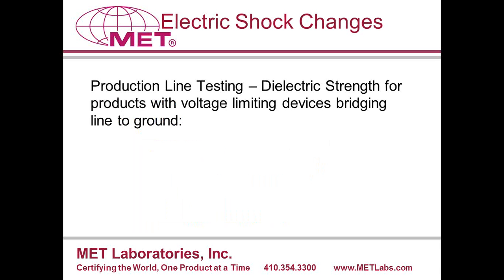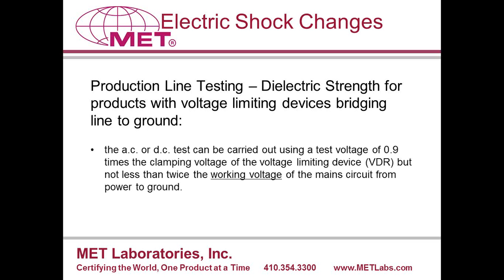Also in third edition, an exception has been made for products with voltage-limiting devices such as VDRs, bridging basic insulation between line and ground. The production line dielectric strength test voltage can be lowered. If you have such a component, you need to determine the working voltage for your power supply that must be used to determine the minimum voltage. This can be higher than the rated voltage because it is the voltage across the transformer, and this can be stepped up with a switch mode power supply to as much as 900 volts peak. If the working voltage is higher than the voltage limit of your limiting device, or VDR, you need to get a component with a higher limit or remove the component during testing.